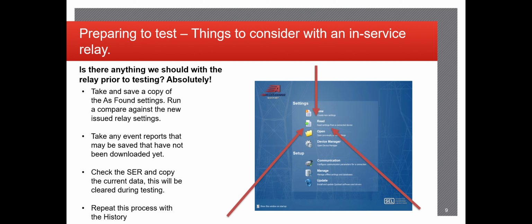So when you're prepping a test, you need to consider quite a few things, especially if it's an in-service relay. Take a save copy of the as found settings. If this is an in-service relay, that means the relay has a settings file in there that was being used prior to whatever you're doing for upgrades. In case anything goes wrong or the client even possibly changes their mind about the whole job, you want to make sure you have the saved file of the as found settings, which means pretty much the file that's in the relay when you first get on site.